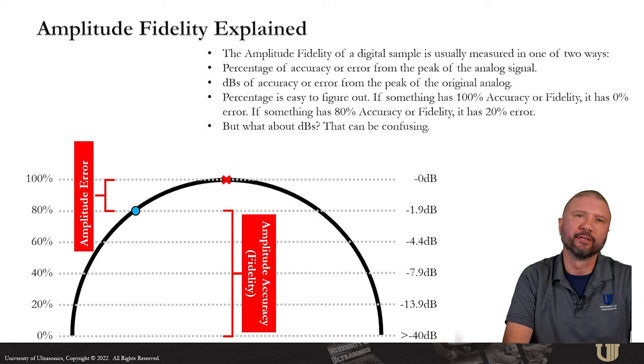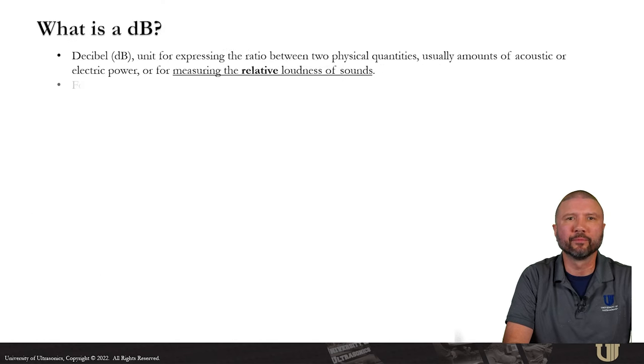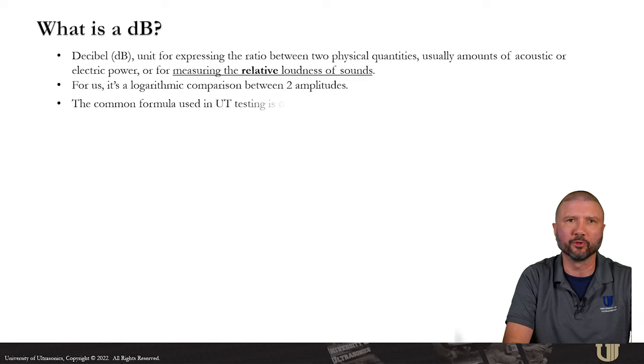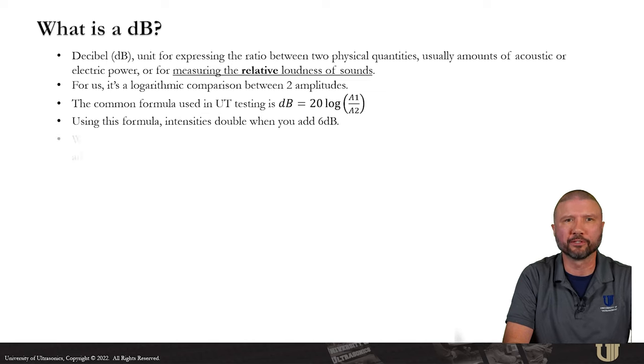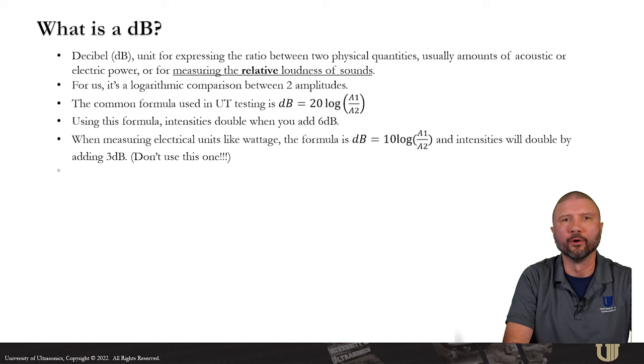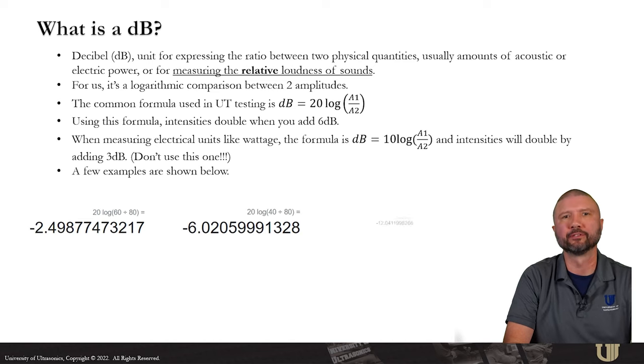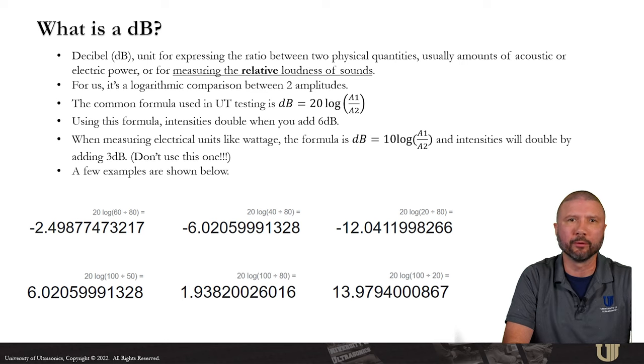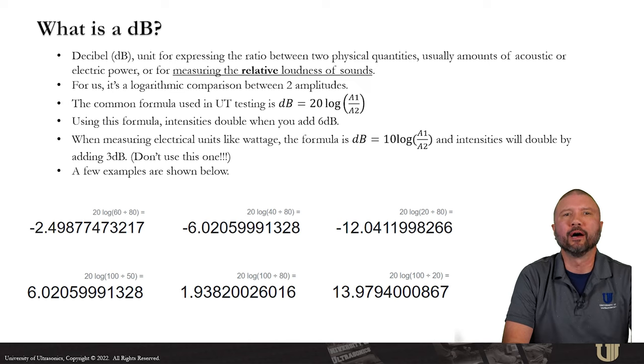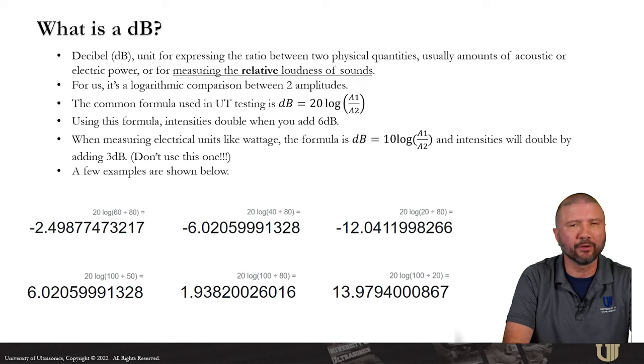But what about dBs? That can be a little bit confusing. A dB or decibel is a unit for expressing the ratio between two physical quantities, usually amounts of acoustic or electric power or for measuring the relative loudness of sounds. For us, it's simply a logarithmic comparison between two amplitudes. The common formula used in UT testing is 20 log amplitude 1 divided by amplitude 2 equals dB. Using this formula, we know that the intensities double when we add 6 dB or they cut in half when we remove 6 dB.